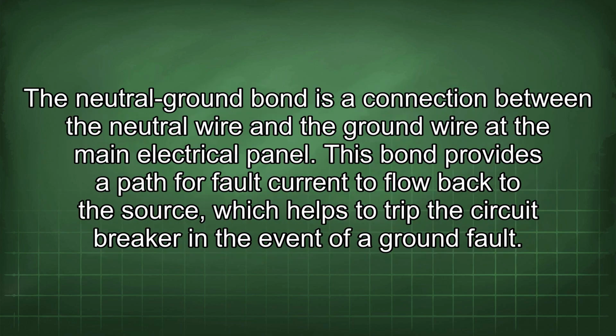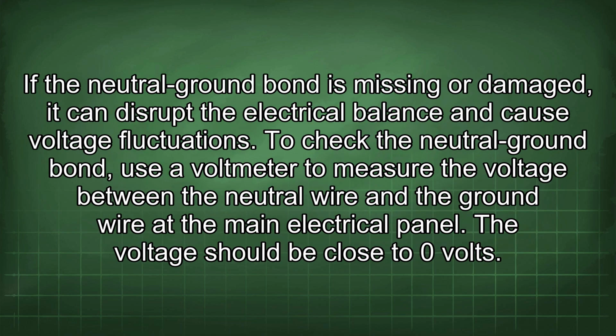The neutral ground bond is a connection between the neutral wire and the ground wire at the main electrical panel. This bond provides a path for fault current to flow back to the source, which helps to trip the circuit breaker in the event of a ground fault. If the neutral ground bond is missing or damaged, it can disrupt the electrical balance and cause voltage fluctuations.